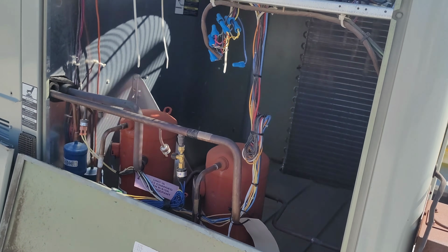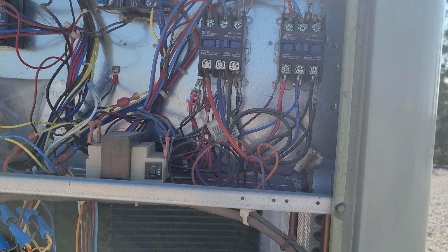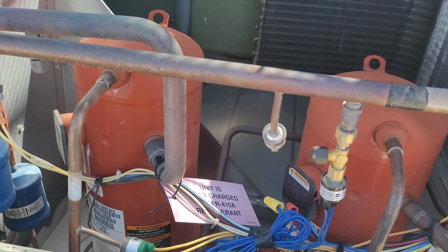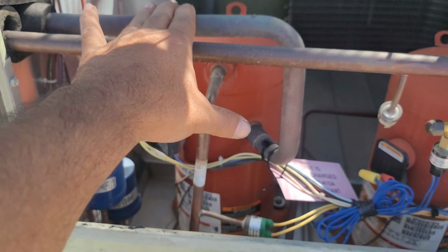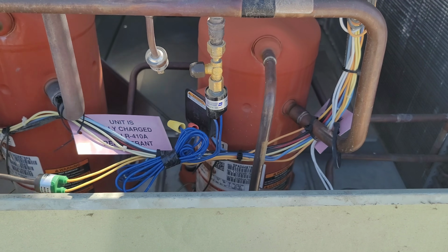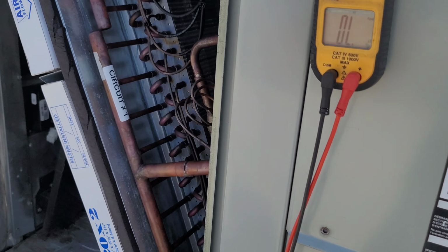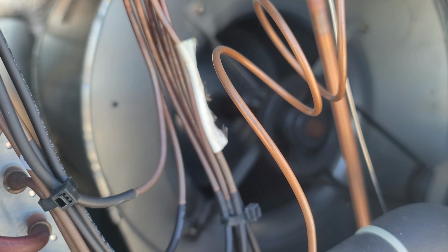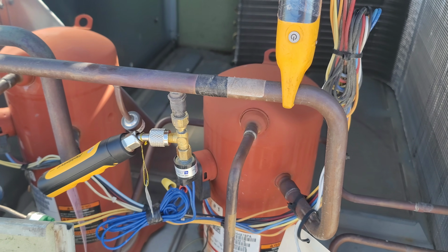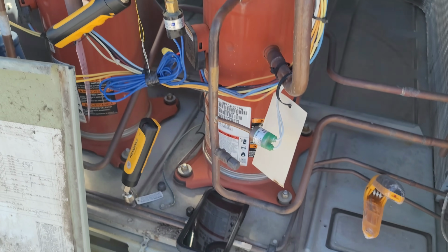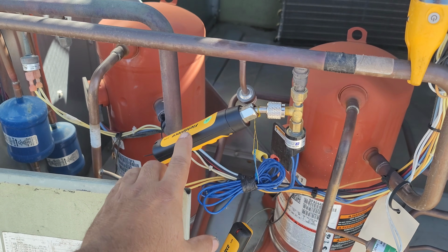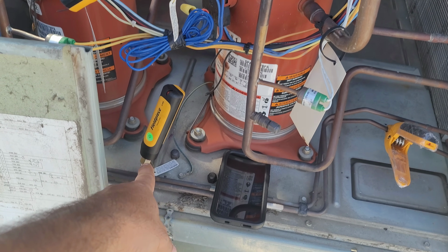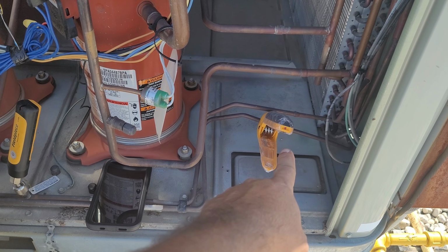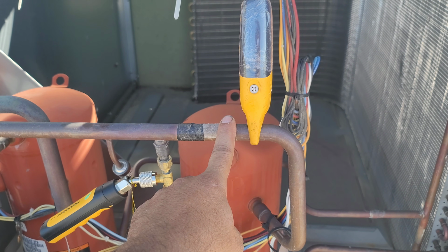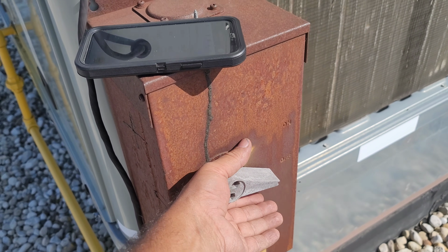Oh wow. So both stages working. Both compressors are running. Getting cold. Getting cold. Hot. Hot. Blower is running. Okay, so next step is we're gonna check the first stage and the second stage refrigeration. So for that I have connected my wireless probe on suction line, another one on liquid line, and temperature probe on liquid line and suction line. So all are synchronized with my software. Press turn on.